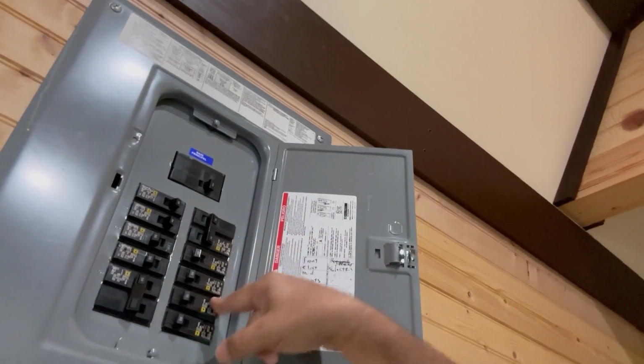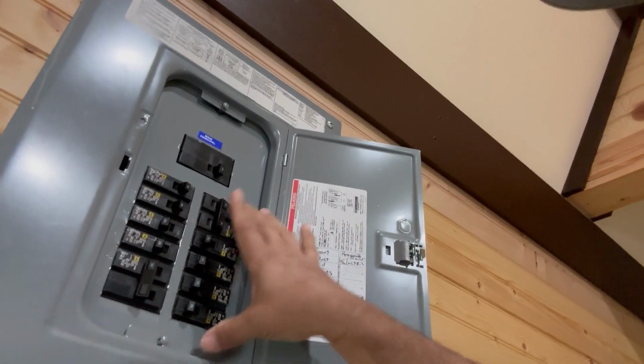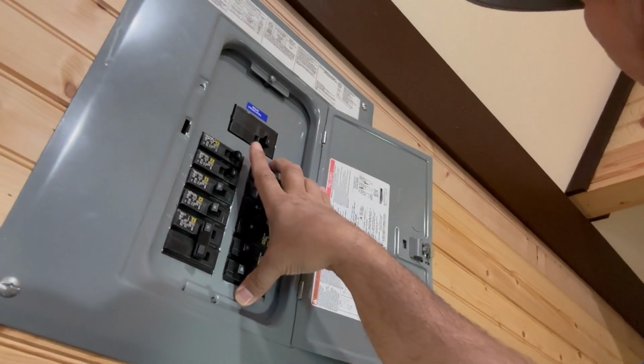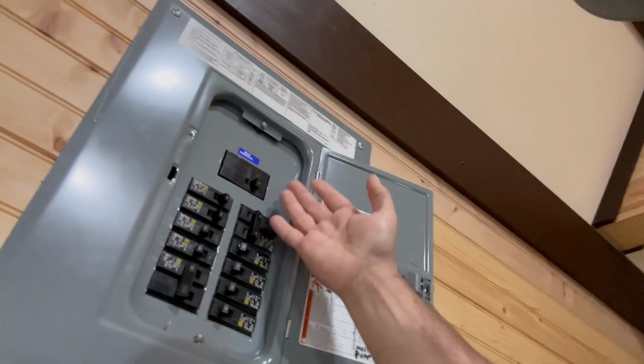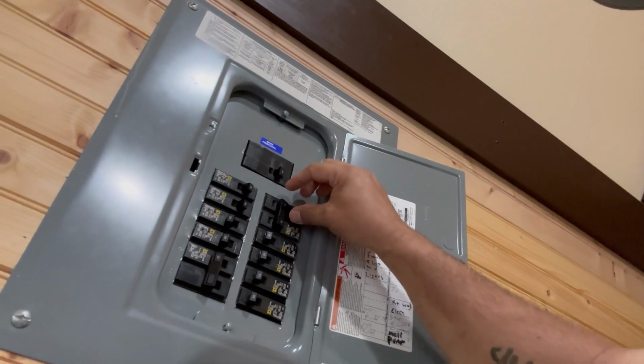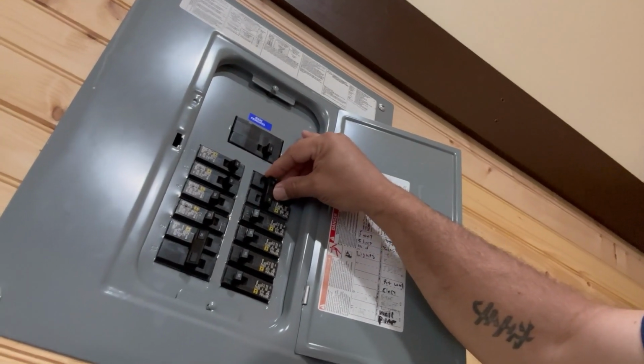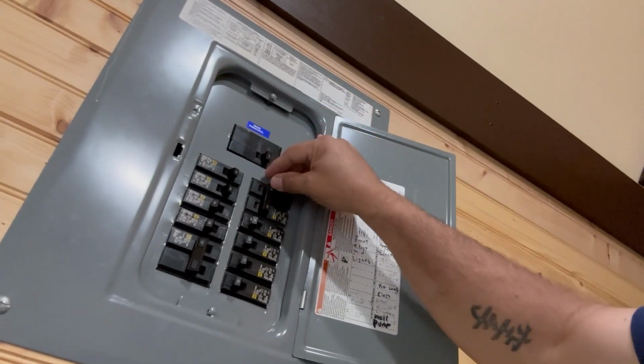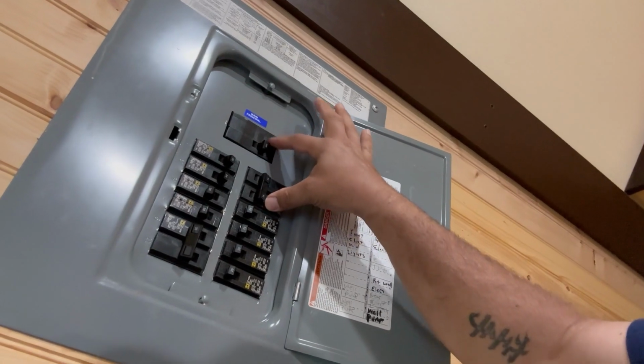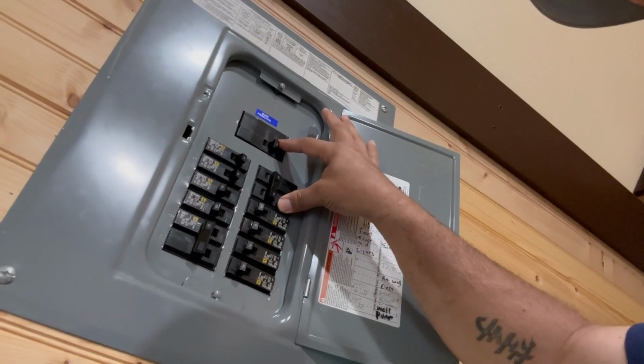Now I could have used breakers here, but I would have only used breakers here if I was doing this with grid tie mode and I was using a generator interlock switch. This here is for a generator, right? So I would need to put the interlock switch here if I was connected to the grid.